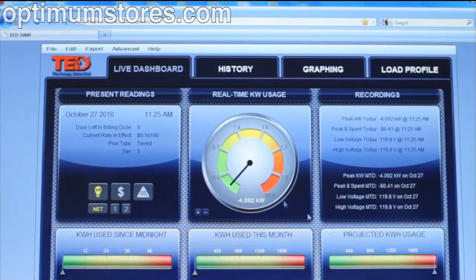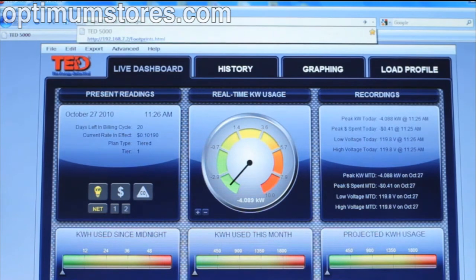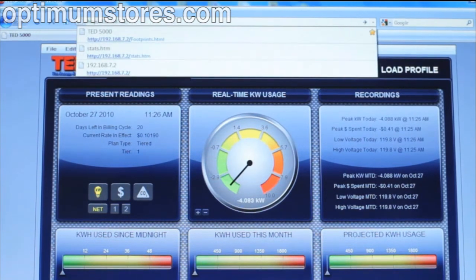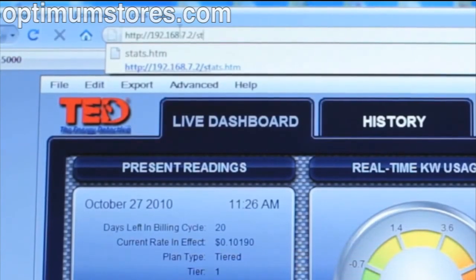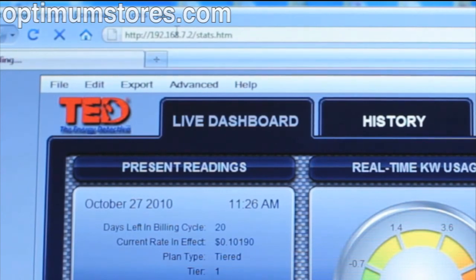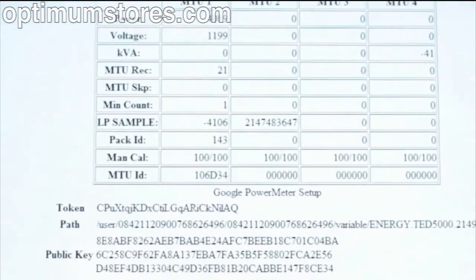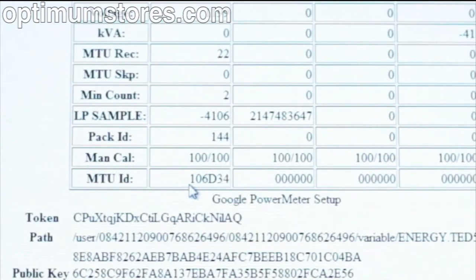If you have questions about your readings at this point, you will want to look at the Diagnostics page, or the Stats page as we call it. Go to your browser and backspace out the Footprints.html from the address. Replace this with Stats.htm — that's S-T-A-T-S dot H-T-M — and hit Enter. Note that your MTU IDs, if properly saved, should be in the table.